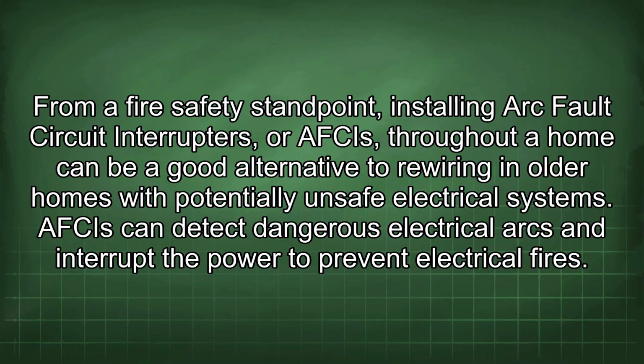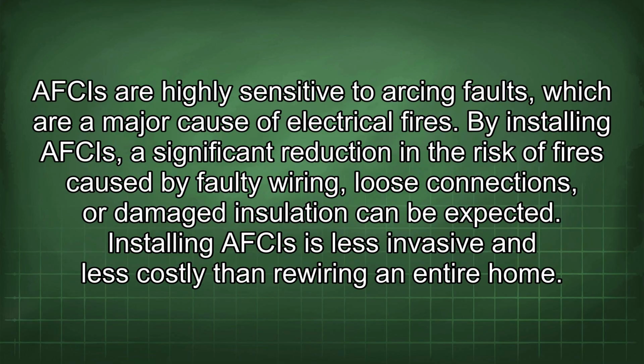From a fire safety standpoint, installing arc fault circuit interrupters, or AFCIs, throughout a home can be a good alternative to rewiring in older homes with potentially unsafe electrical systems. AFCIs can detect dangerous electrical arcs and interrupt the power to prevent electrical fires. AFCIs are highly sensitive to arcing faults, which are a major cause of electrical fires.